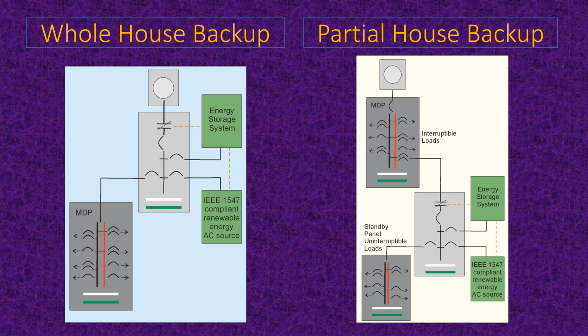So here we allow some of the big loads to be interrupted. Maybe that's that 5-ton air conditioner, and shut off at a sub feed from that interruptible load panel, which feeds an uninterruptible load panel of relatively smaller loads. And then we do the same thing, make the energy storage and the solar available to the standby smaller uninterruptible loads, which might be more on the order of 10 to 20 kilowatt hours a day. It's all a matter of how many batteries you want to pay for and how much room you have on your roof for solar to make sure those batteries stay charged. So we're going to take a look at what it takes to make these things happen.